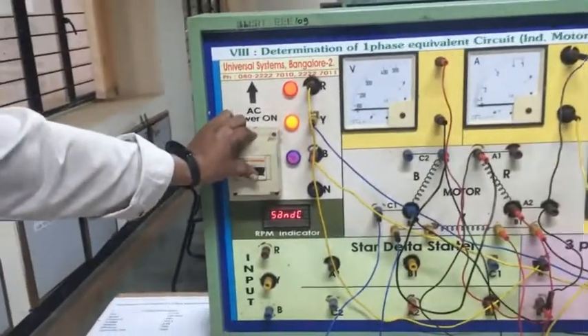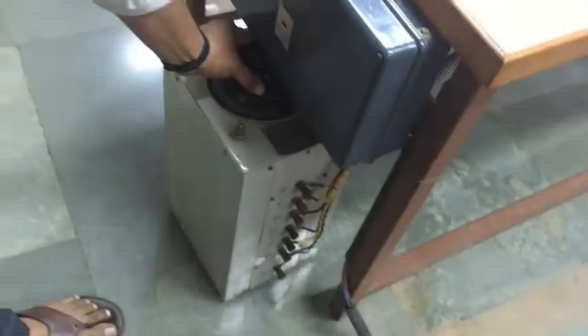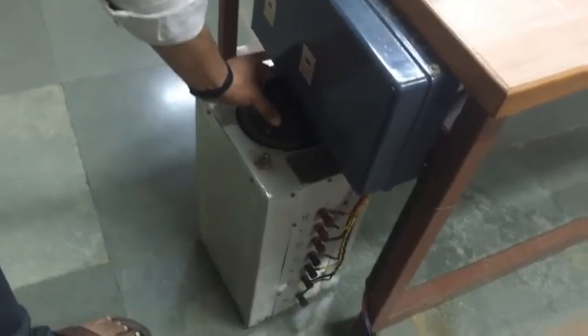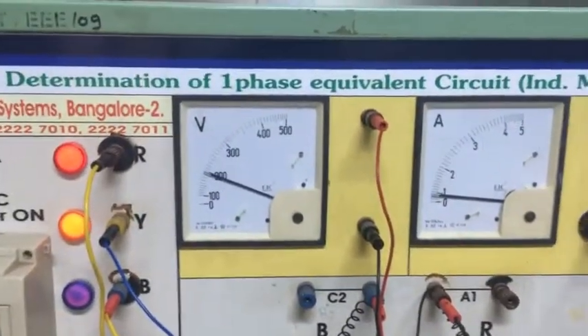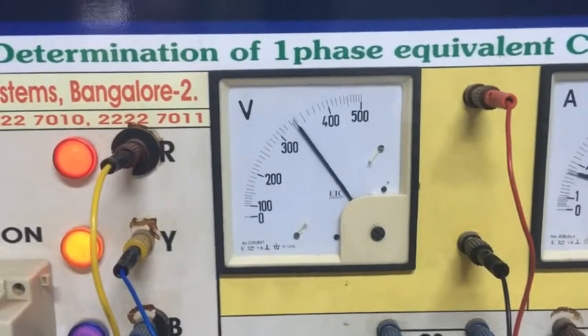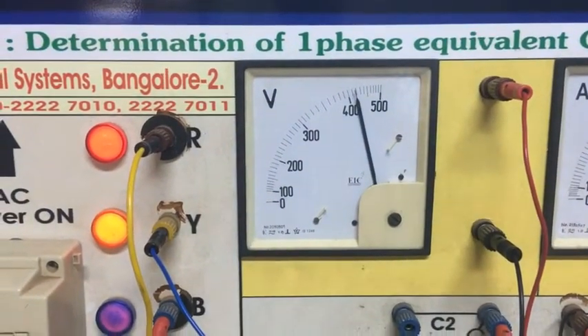Now once the connections have been carried out, switch on the three-phase supply. Before switching on, see that the load is free and the motor is not rotating. Switch on the main supply MCB. Now come towards the auto transformer and slowly vary it, and check whether the rotor is rotating. Once the rotor starts rotating, apply the full voltage, that is the no load voltage, by varying the auto transformer up to 450 volts.